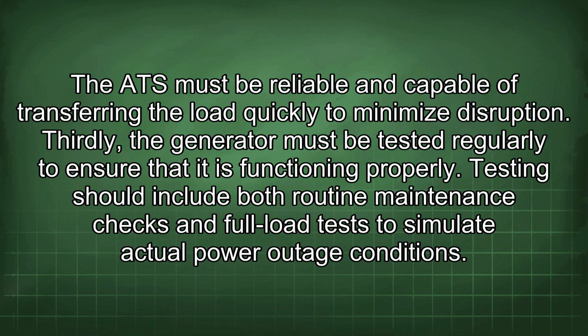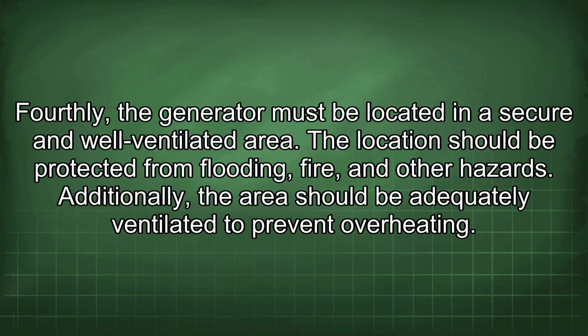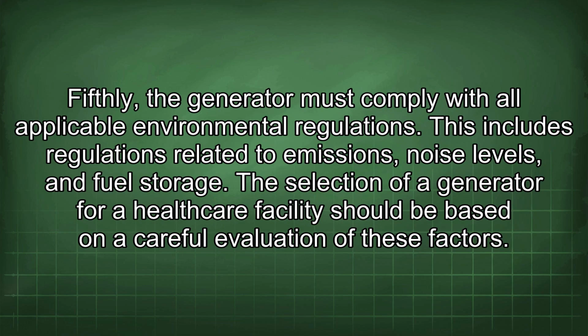Thirdly, the generator must be tested regularly to ensure that it is functioning properly. Testing should include both routine maintenance checks and full load tests to simulate actual power outage conditions. Fourthly, the generator must be located in a secure and well-ventilated area, protected from flooding, fire, and other hazards, and adequately ventilated to prevent overheating. Fifthly, the generator must comply with all applicable environmental regulations, including those related to emissions, noise levels, and fuel storage.